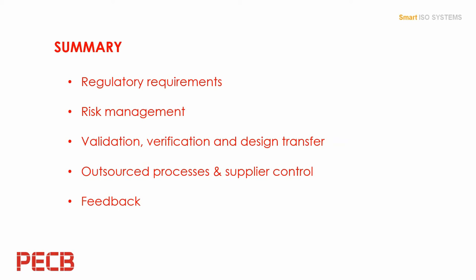Validation, verification and design transfer. The draft standard puts a lot more structure into place around those activities. You must now have plans in place and documented evidence to show you have done validation, verification and the design transfer activities. And the fourth point, outsourced processes. The draft standard requires that organizations do a lot more when it comes to outsourcing processes and put into place controls for assessing suppliers, again based on risk.